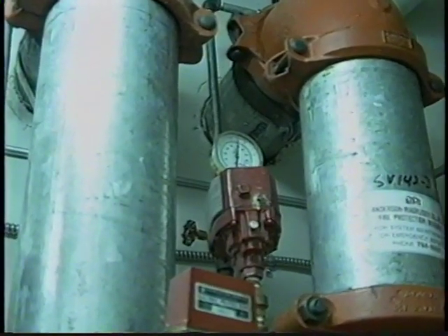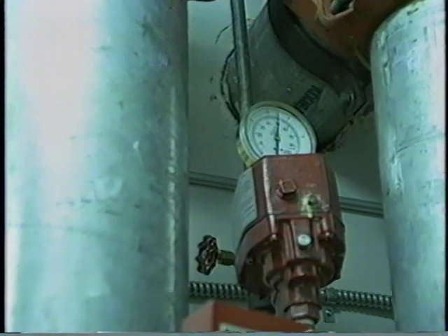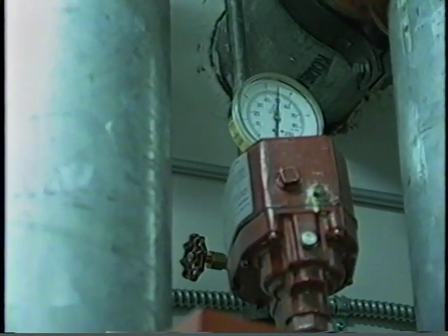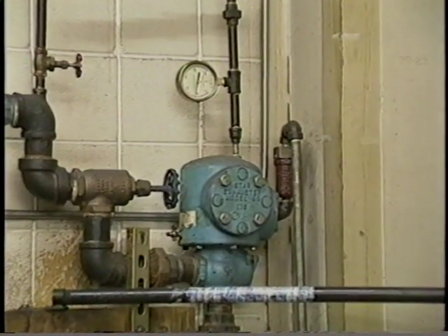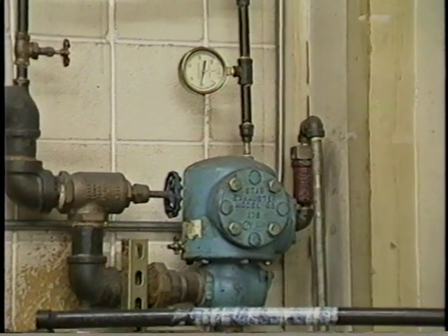This may cause a delay in the water reaching the sprinkler heads, allowing the fire to spread. Systems with a water capacity of over 500 gallons or 2,000 liters are required to have a quick opening device to help speed the release of water to the fire.